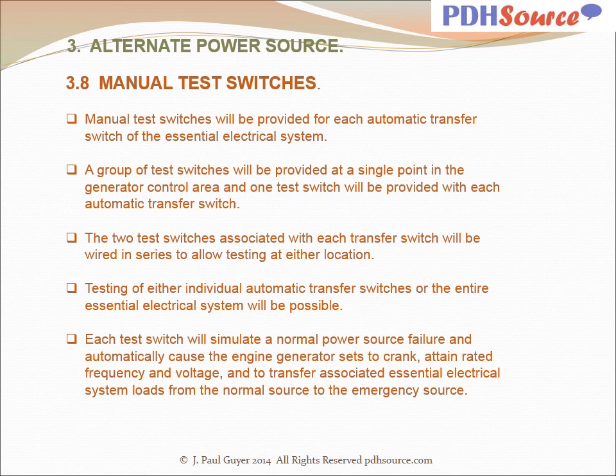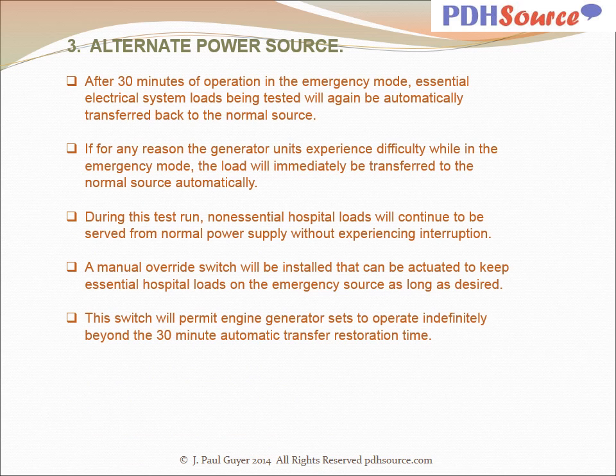Each test switch will simulate a normal power source failure and automatically cause the engine generator sets to crank, attain rated frequency and voltage, and transfer associated essential electrical system loads from the normal source to the emergency source. After 30 minutes of operation in the emergency mode, essential electrical system loads being tested will again be automatically transferred back to the normal source. If for any reason the generator units experience difficulty while in the emergency mode, the load will immediately be transferred to the normal source automatically. During this test run, non-essential hospital loads will continue to be served from normal power supply without experiencing interruption.